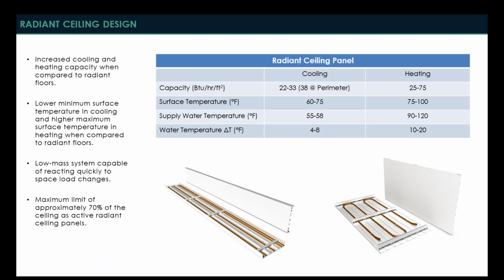Now let's move on to radiant ceiling design and look at some of the design parameters for these types of systems. You can see here that from a cooling and heating capacity standpoint, we've definitely bumped up a little bit from what we were looking at with the radiant floor system. So a typical radiant cooling panel system is going to give you anywhere between 22 and 33 BTUs per hour per square foot. The 22 would be on the low end, and that would be more indicative of a drywall panel application.